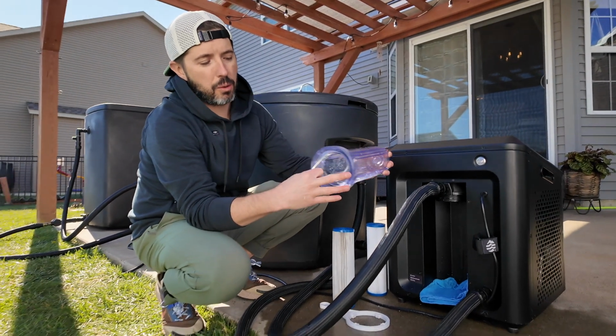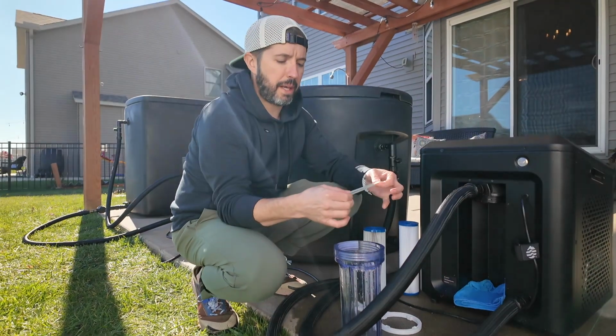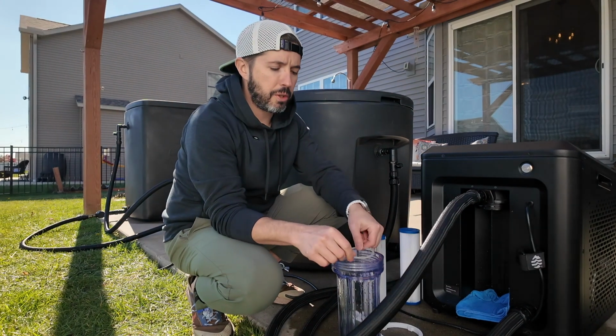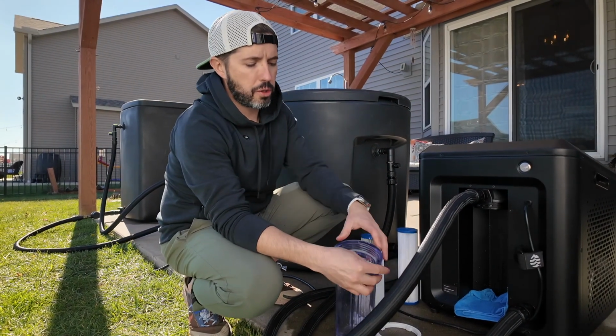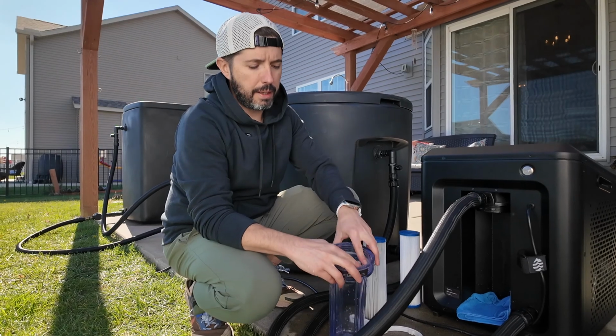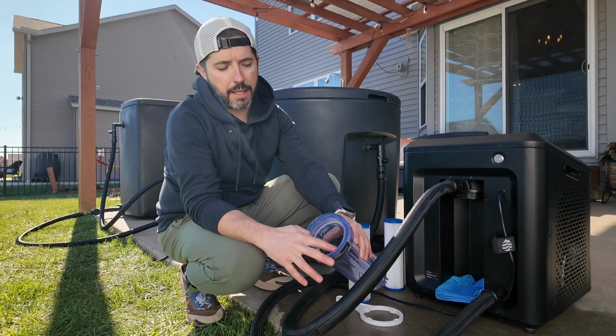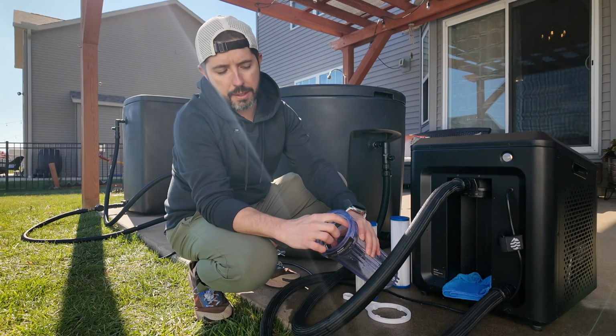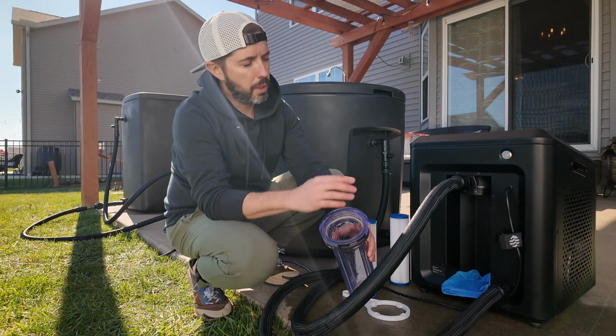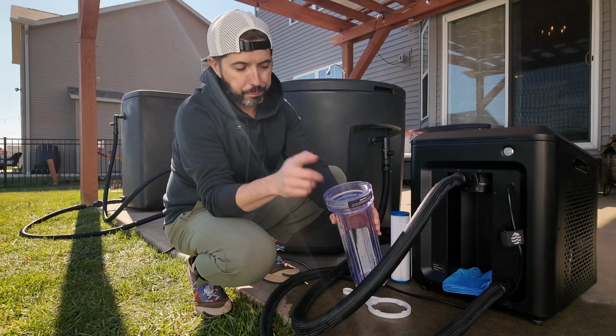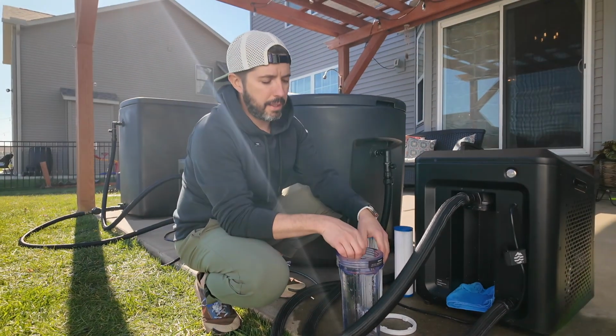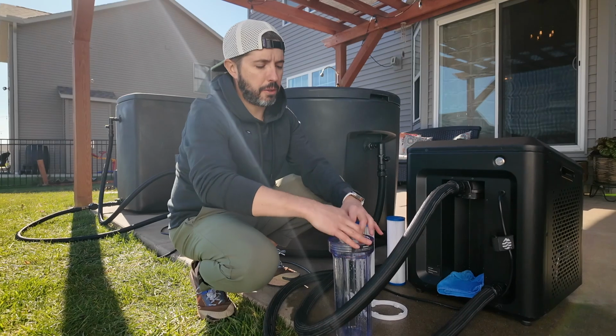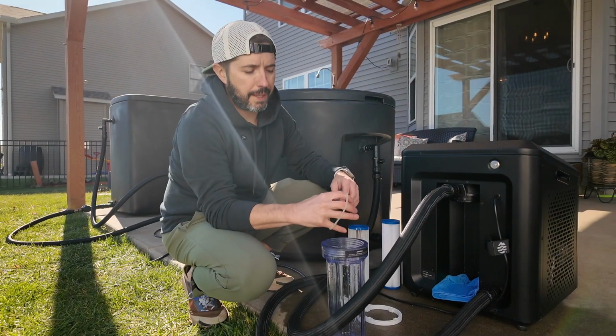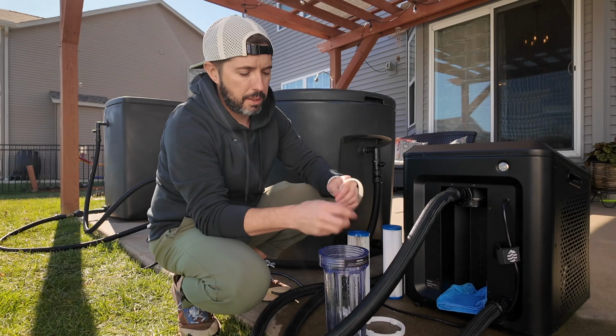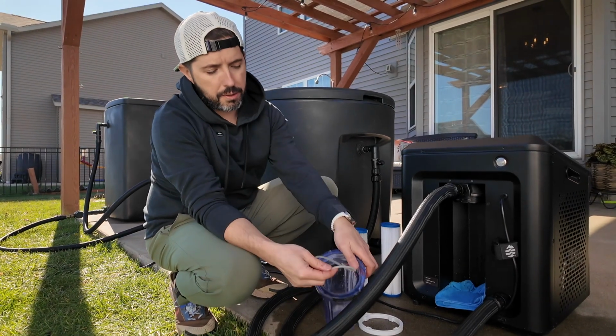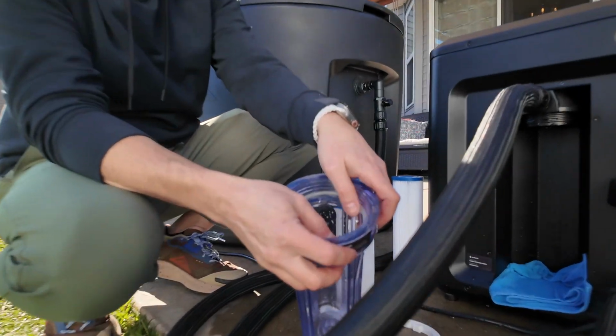The other thing to note about this O-ring is that it's pretty flexible, and you want to make sure it's sitting inside the groove towards the outside wall. If it hangs over the inside edge of the filter bowl, like this, it won't seal, and when you go to turn it on, it'll spray water everywhere. So a good tip is, if it doesn't look like it's sitting the way you want, put your hands around it and give it a slight stretch—not too much, or you'll overstretch it—and that'll make it easier to get it to sit in its seat where it belongs.